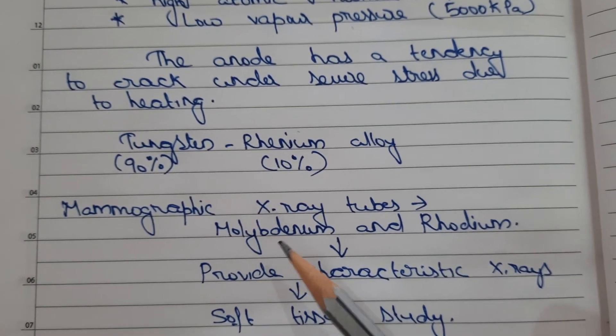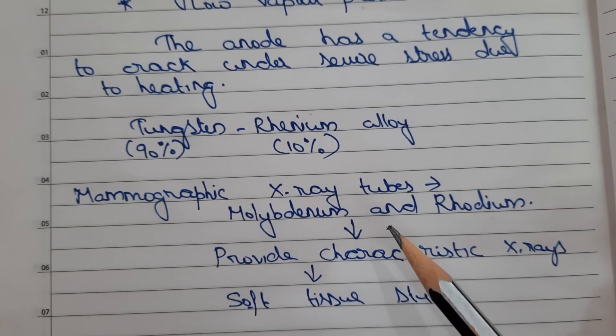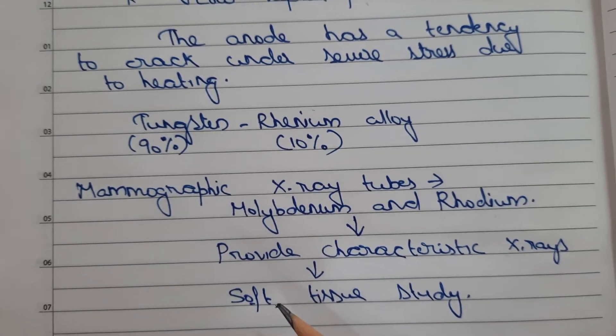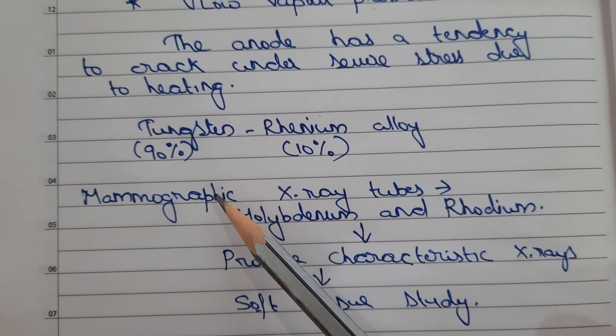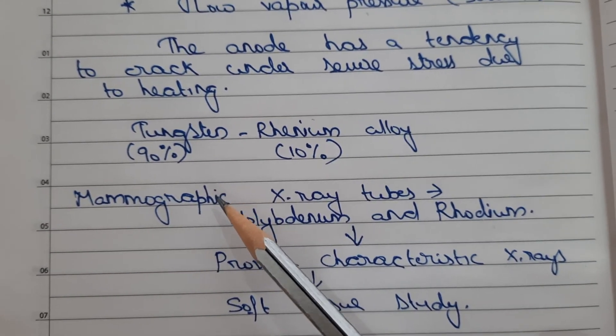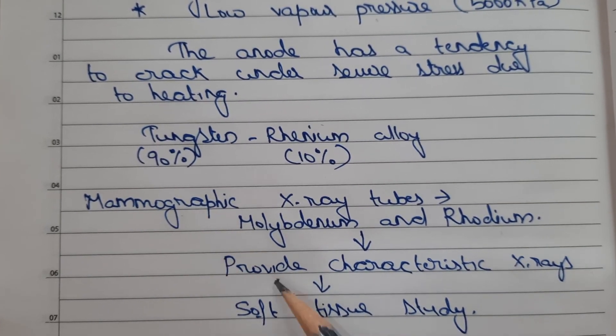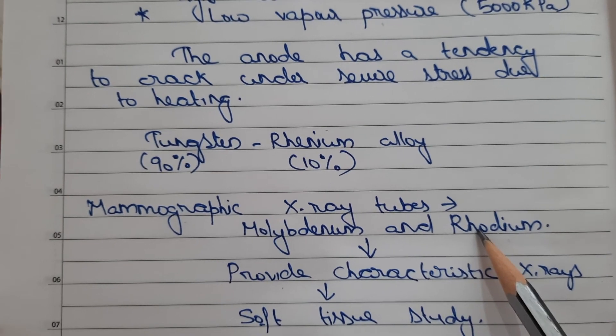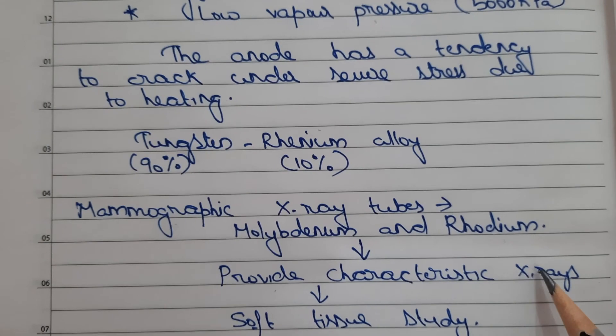For mammographic x-ray tubes, we can use molybdenum and rhodium as target materials. These materials provide characteristic x-rays which enable soft tissue study. Since mammography is a study of breast tissue — a soft tissue study — molybdenum and rhodium are preferred as they produce the characteristic x-rays needed.